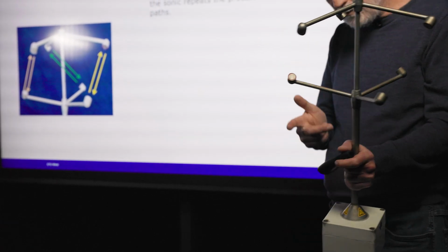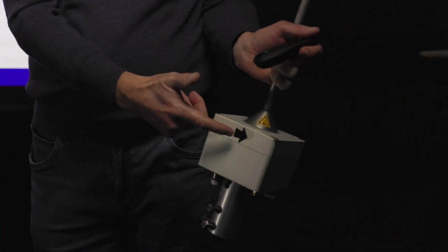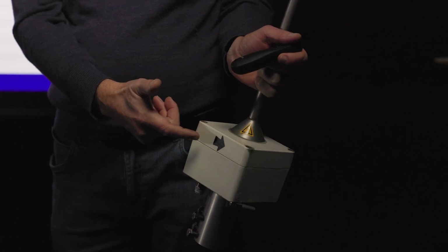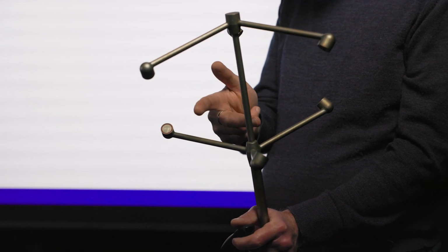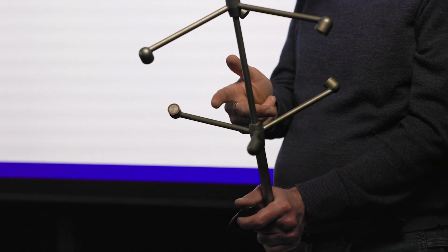Y traditionally points to the north, so you can see there's a north arrow on the side of the instrument to tell us how to align the instrument when we put it on the mast. And then of course the remaining axis, the x-axis, will be perpendicular to that in the horizontal plane, so pointing to the east or to the west.